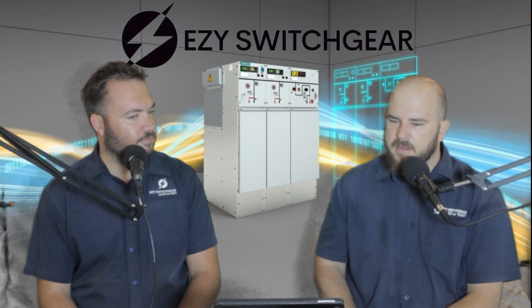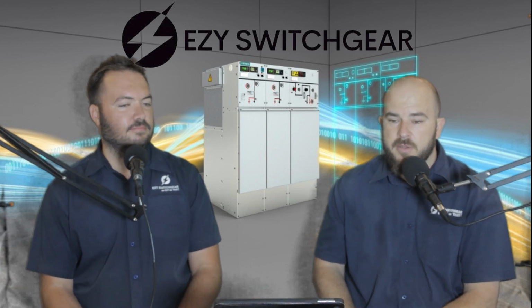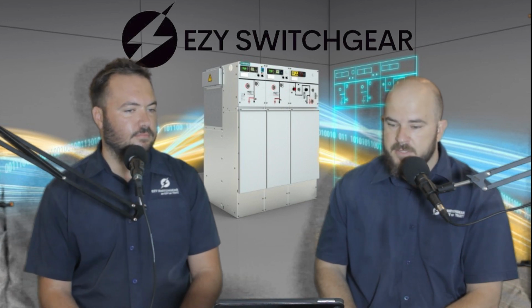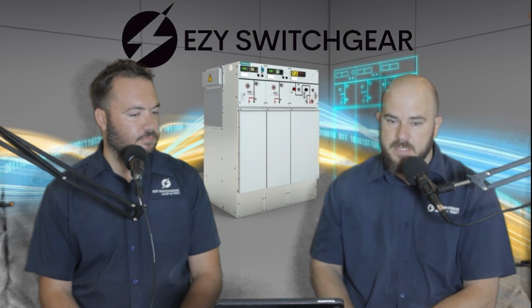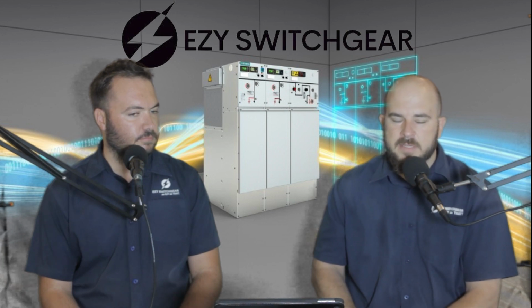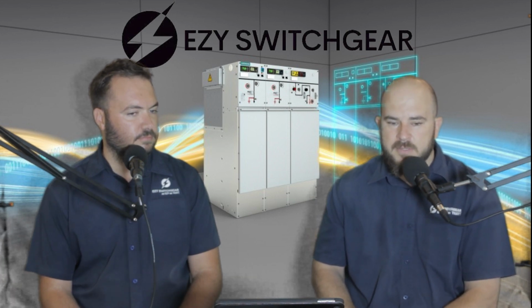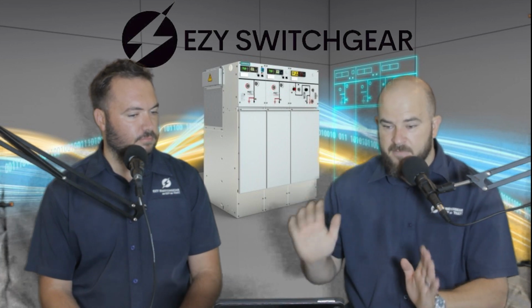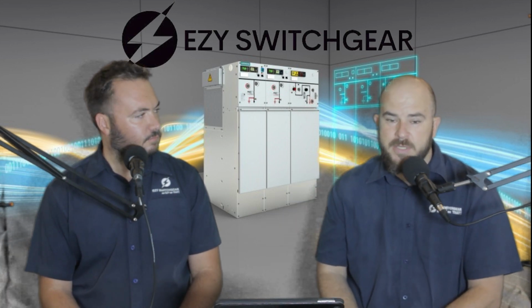But the rated voltages that we normally use are 6,600, 11,000 volts, and then 22,000 and 33,000 volts in South Africa. In other countries, it can be similar to this: 12,000, 15,000, and 36,000 volts. So it depends on which country you are in, but that is the field which the industry calls the medium voltage field. Then what is switchgear?